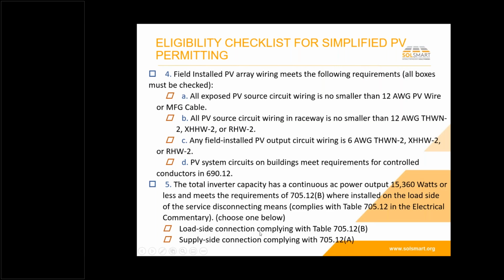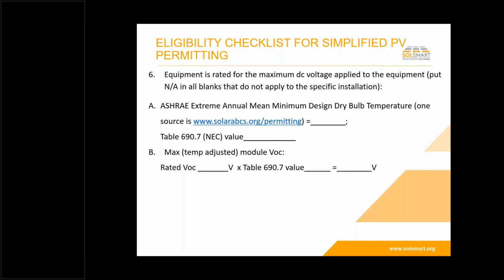Load side connection complying with 705.12b, and supply side connection complying with 705.12a, and that's just the parts of the code that are relevant there. Equipment's rated for the maximum DC voltage applied to the equipment. So really the only thing we have to worry about on the electrical side is making sure that the ratings, which are temperature dependent and location dependent, that's the real location dependent issue, meet the requirements. And we have guidance. Here's a website that tells us what the ASHRAE extreme annual mean minimum dry bulb temperature is for your area, and you can look that up.